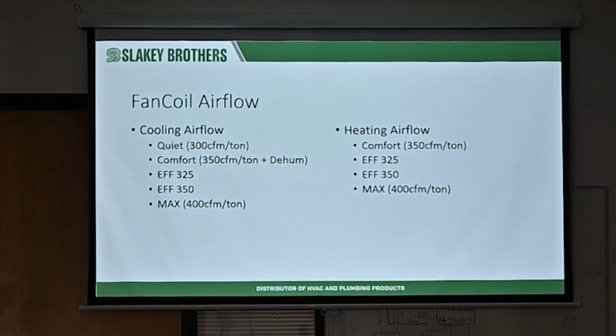Airflow, you're going to see we'll breeze through the furnaces as well pretty quickly because airflow setup is the same. Heating, cooling, this is for a heat pump because of the fan coil. But if it's a furnace, you're going to see it's pretty much the exact same thing. You have options of 300, 325, 350, max 400 CFM per ton. Everything comes default comfort, 350. If you ever start up a unit and you're like, man, I got a 22-degree split, but everything's perfect, that might be one you might want to reconsider. Instead of 350 CFM per ton, leave it at 400 CFM per ton.